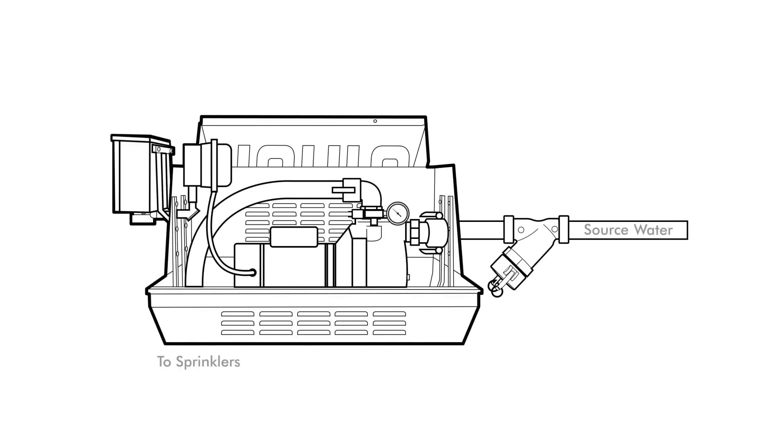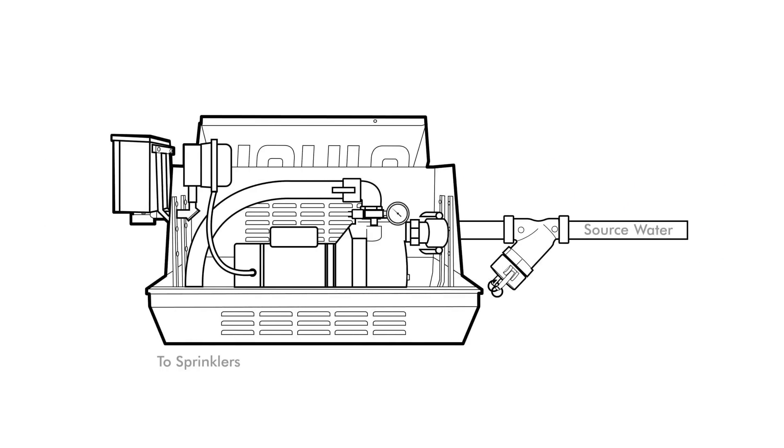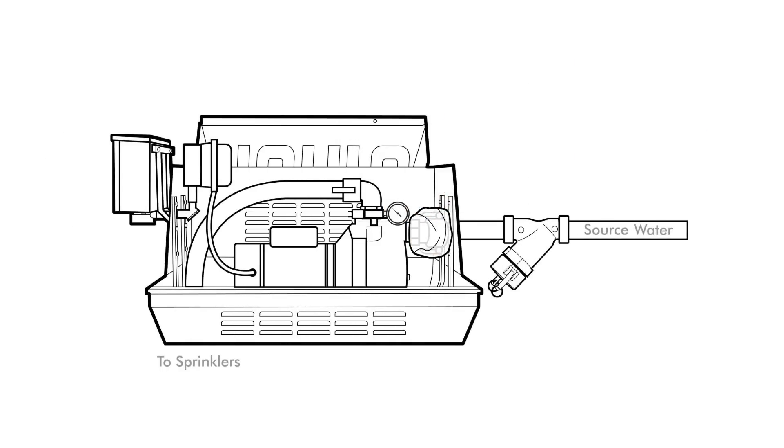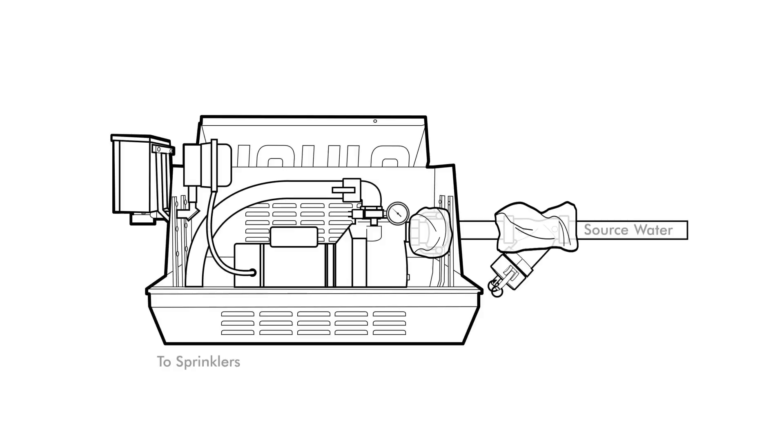An easy way to check for air leaks is to wrap plastic wrap around a few potential problem areas on the suction side. These can include the filter, any gate or ball valves, any threaded parts or PVC glued on the suction side.